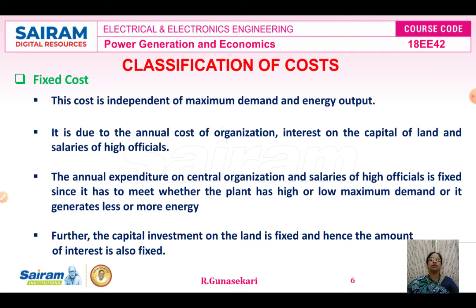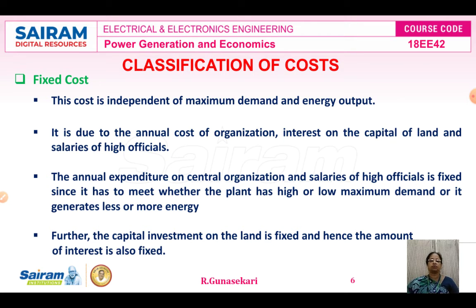Now we studied about the classification of cost. The first cost is fixed cost. This cost is independent of the maximum demand and energy output. The fixed cost is due to the annual cost of the organization, interest on the capital of the land, and salaries of higher officials. The annual expenditure on central organization and salaries of high officials is fixed whether the plant has high or low maximum demand or generates less or more energy. The capital investment on land is fixed, and therefore the amount of interest is also fixed.